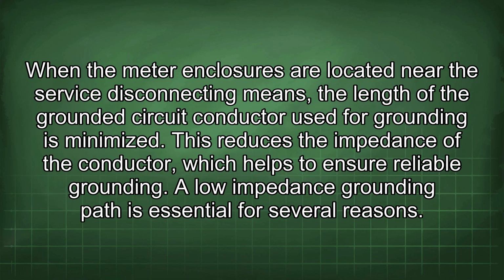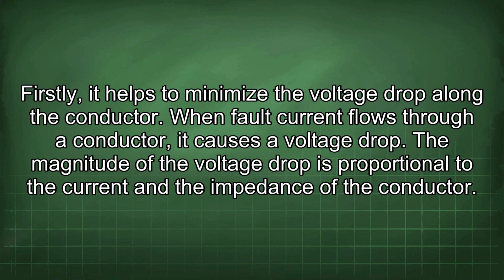When the meter enclosures are located near the service disconnecting means, the length of the grounded circuit conductor used for grounding is minimized. This reduces the impedance of the conductor, which helps to ensure reliable grounding. A low-impedance grounding path is essential for several reasons. Firstly, it helps to minimize the voltage drop along the conductor. When fault current flows through a conductor, it causes a voltage drop.